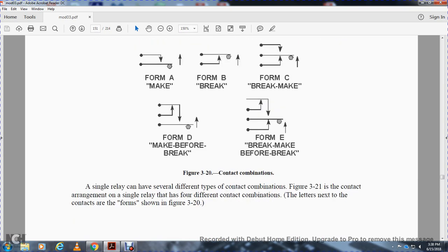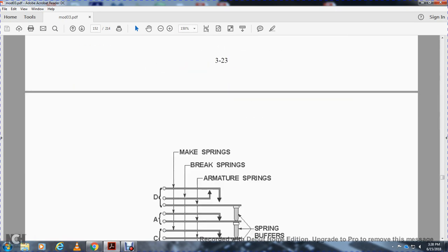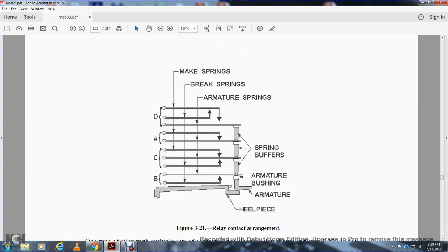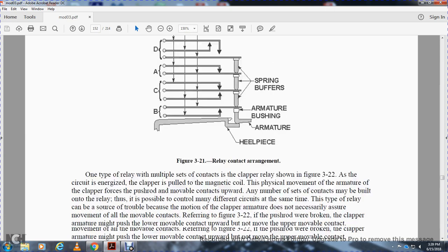A single relay can have several different types of contact combinations. Figure 321 shows a contact arrangement of a single relay with the 4 different contact combination letters next to the contacts, as in the forms shown in figure 320. Figure 321 shows the relay contact arrangement. So: the make springs, break springs, armature springs, D, A, C, and B, spring buffers, armature bushings, armature heel piece.